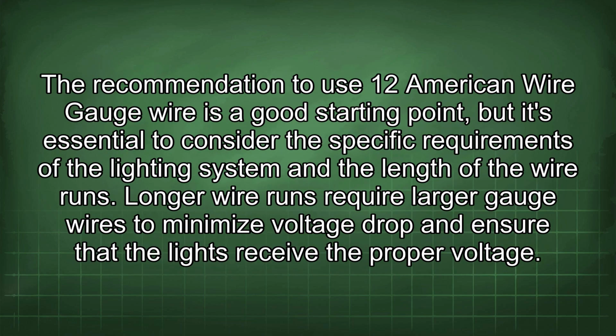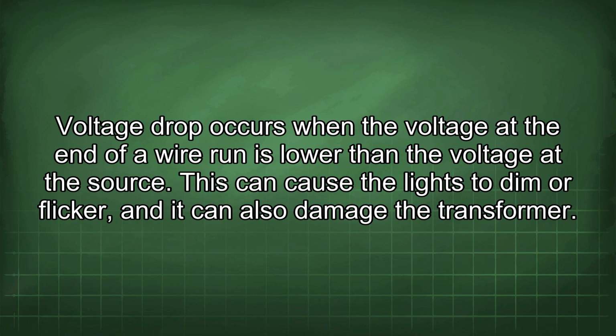The recommendation to use 12 American wire gauge wire is a good starting point, but it's essential to consider the specific requirements of the lighting system and the length of the wire runs. Longer wire runs require larger gauge wires to minimize voltage drop and ensure that the lights receive the proper voltage. Voltage drop occurs when the voltage at the end of a wire run is lower than the voltage at the source. This can cause the lights to dim or flicker, and it can also damage the transformer.